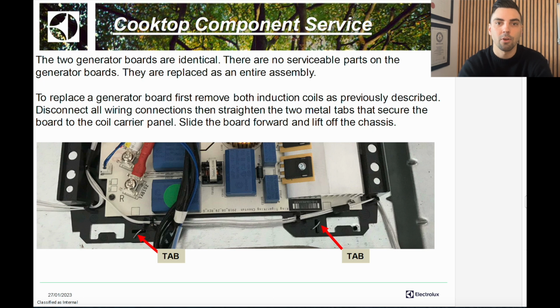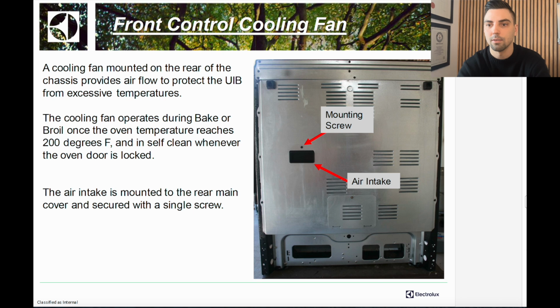The 2 generator boards are identical. There are no serviceable parts on the generator boards. They are replaced as an entire assembly. To replace the generator boards, first remove both induction coils as previously described. Disconnect all wiring connections, then straighten the 2 metal tabs that secure the board to the coil carrier panel. Slide the board forward and lift off the chassis.